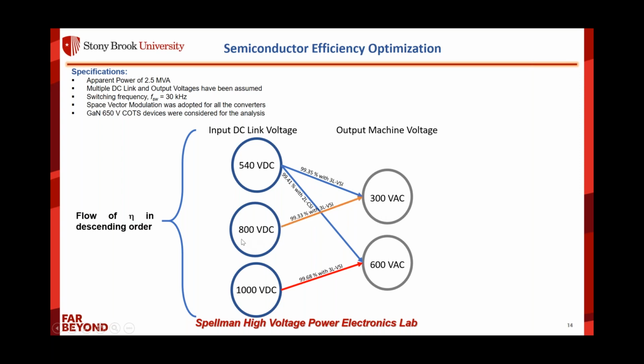If I'm going to use 800 volt DC to generate 300 volt AC output, my efficiency is around 99.33% going with a three level VSI. And if I'm stepping down from a higher voltage, obviously I'm losing efficiency.